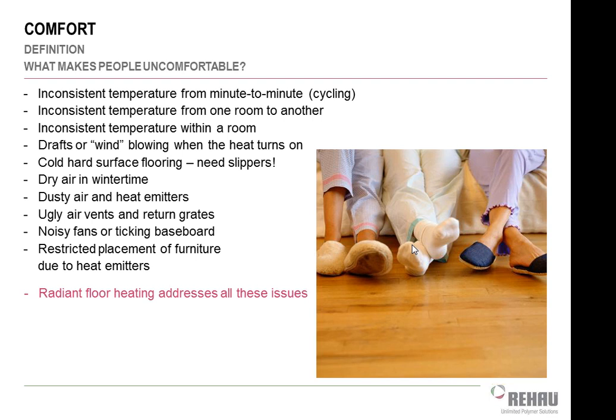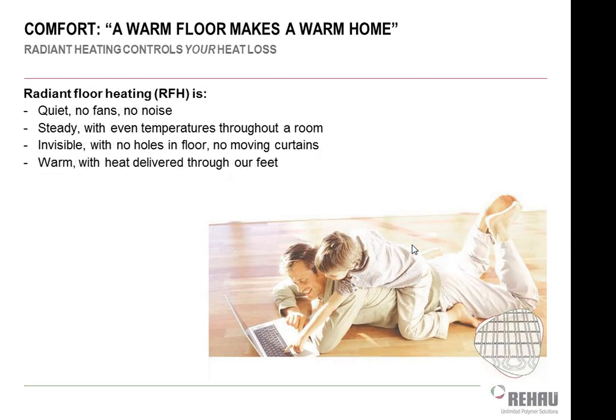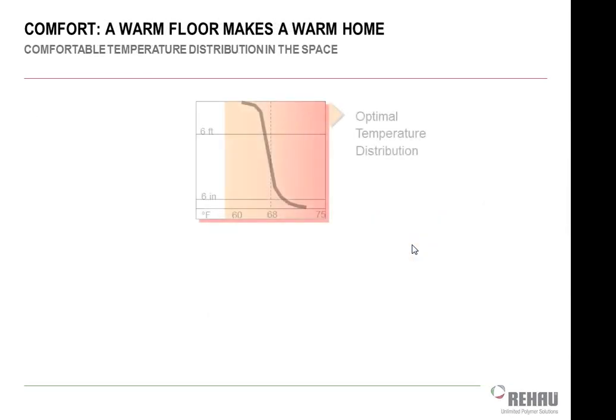So the basic premise of the radiant system is to get the entire system where the consumer cannot see it at all, give them very even temperature and comfort so they don't know that there's anything going on in the background, and make it as quiet as possible. Those are kind of all the goals of these types of systems. So no fans except for the blower motor on the condensing boiler itself, which hopefully is down in your basement where you won't even notice it. Even temperatures from floor to ceiling, from north to south, east to west, that kind of thing.